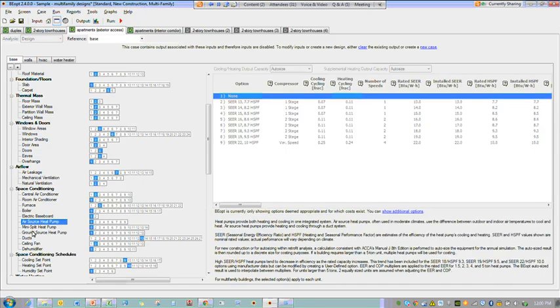In addition to these new technologies, we have updated the way that heat pumps get sized. So this applies to air source heat pumps, mini split heat pumps, and ground source heat pumps. And previously, we've always used the ACCA Manual J or S approach to sizing equipment, which always uses the design cooling load to size heat pumps.